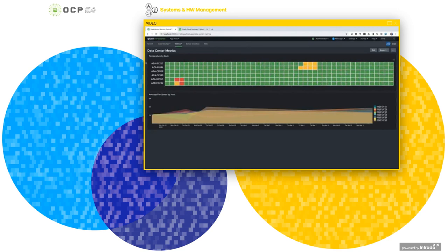Next, we'll go look at some data center metrics. Here we can see the temperature by rack. So in this example, you can see we had some hotspots on systems GC160 and ER232, as well as some excursions elsewhere in the data center. And down below, we can see what the average speed of the host was.